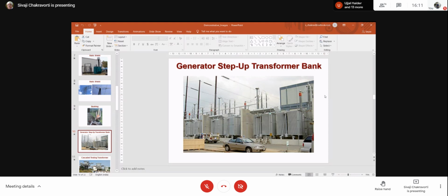So what we do, we take smaller transformers, and the individual phases are just single phase transformers. And here you can see two transformers in parallel makes phase A. Second one, phase B. Third one, phase C. So what happens now, 500 megawatt, first of all, is divided into 3 parts, and then each part is divided into 2. So each one comes down to some 80 megawatts, 85 megawatts. That is manageable for one unit.